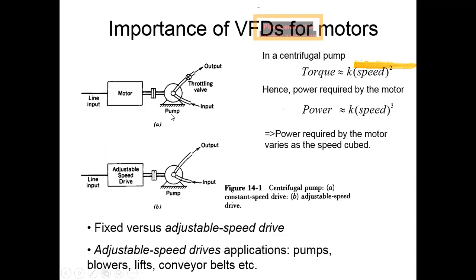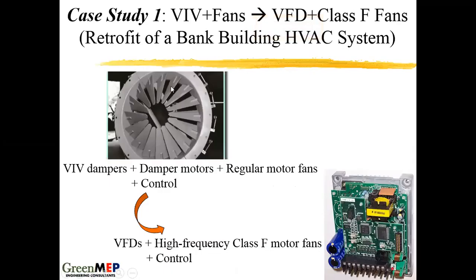Now these are some simple examples. Now this is not water flow. This is air flow. You may have seen these things. This is variable inlet vane, dampers, right? Just like a valve controlling the flow here, the fan is running at a constant speed, motor is running at a constant speed. You open and close these dampers, these flaps to control the flow. So what happens is air is coming and hitting here, which is an energy loss, right?